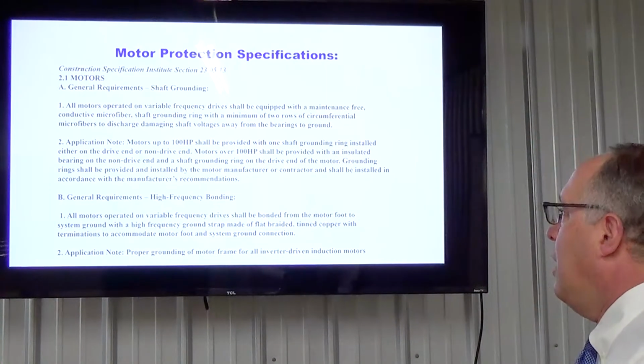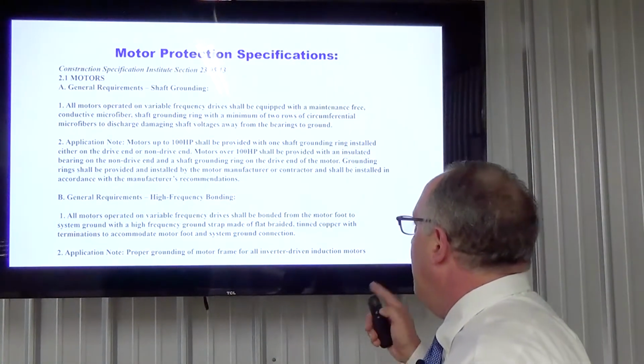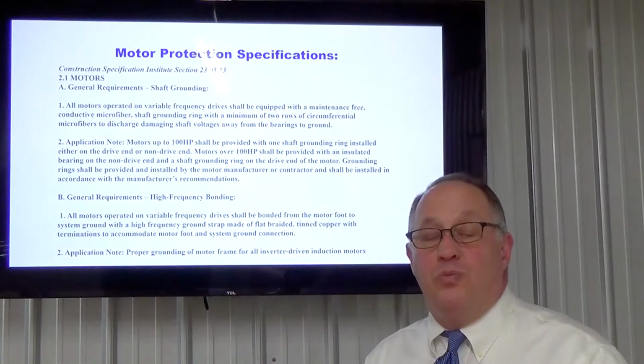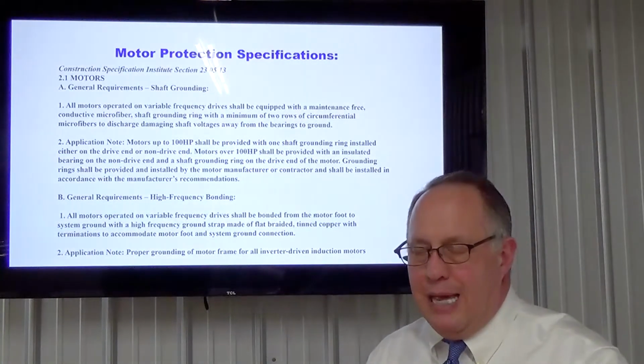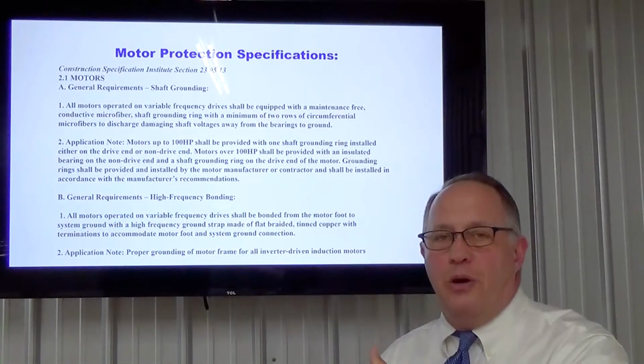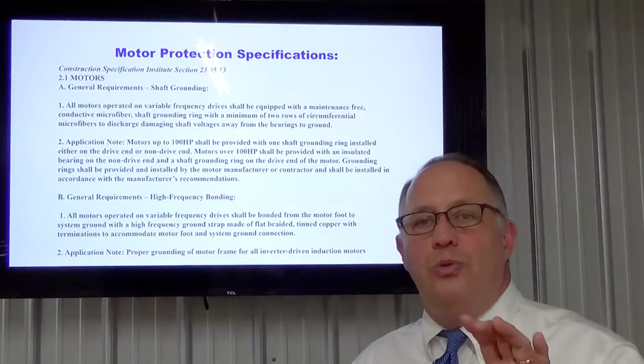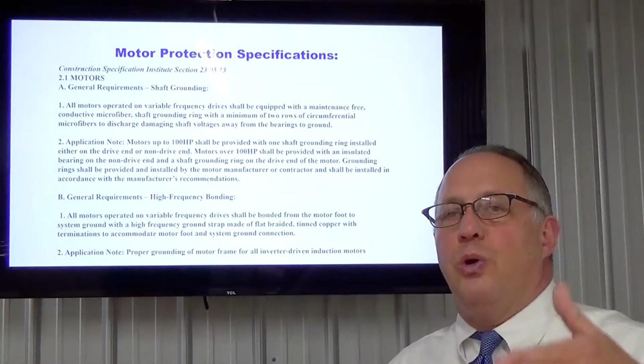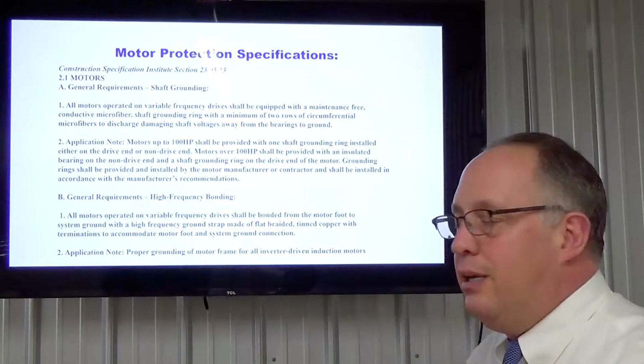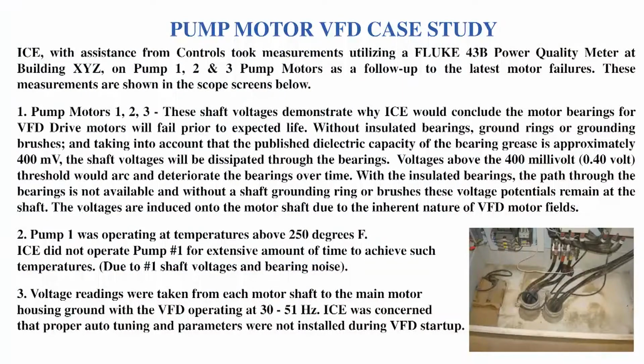High frequency bonding, remember we talked about for larger motors, absolutely. 100 horsepower and above, we need to include that grounding strap because we're going to have those induced high frequency voltages as well.